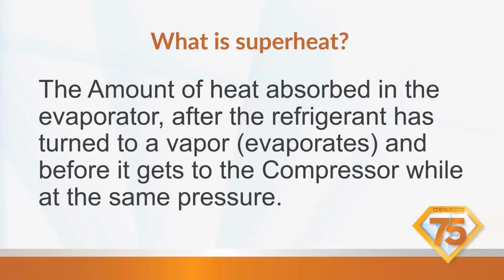What is superheat? We're just touching on all this stuff because we only have an hour. Superheat is the amount of heat absorbed in the evaporator after the refrigerant has turned into a vapor, evaporates, and before it goes to the compressor. It's just like water, the saturation temperature where it turns to vapor and liquid. So we want a superheated vapor coming back to the compressor, at the same pressure. So the pressures are not changing.